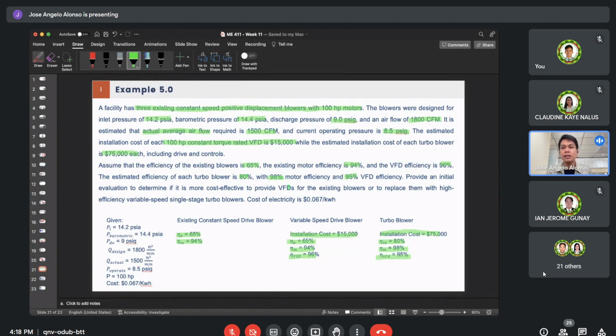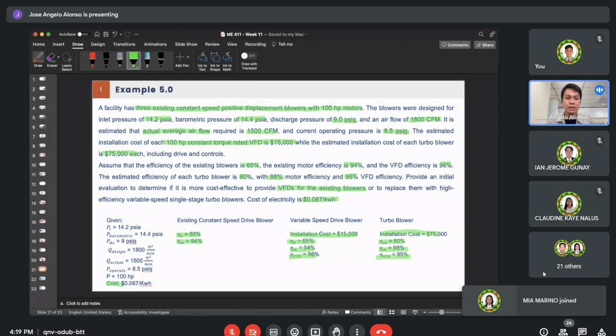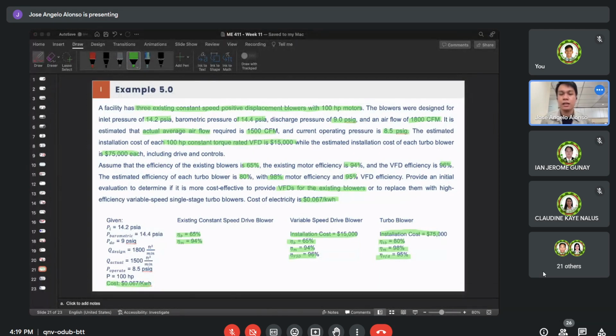Now, what's being asked of us is to provide an initial evaluation to determine if it is more cost-effective to provide VFD for the existing blowers or to replace them with the high-efficiency turbo blowers. The cost of electricity is $0.067 per kilowatt-hour. So our case here is comparing the savings, or whether it's cost-effective to install a VFD or a turbo blower, in exchange for retaining the existing constant speed setup.